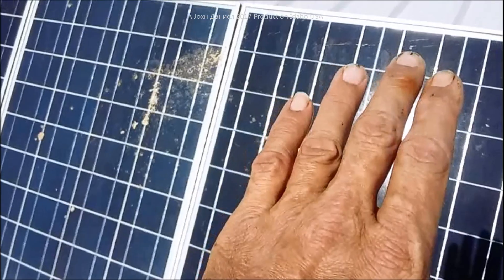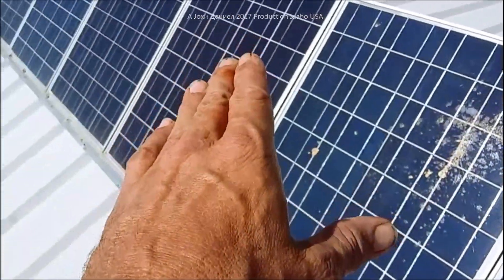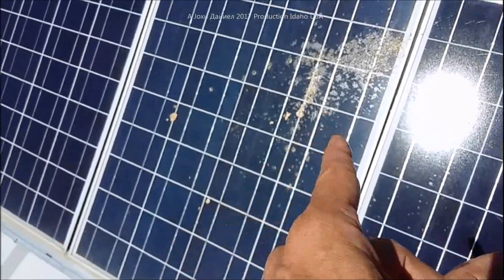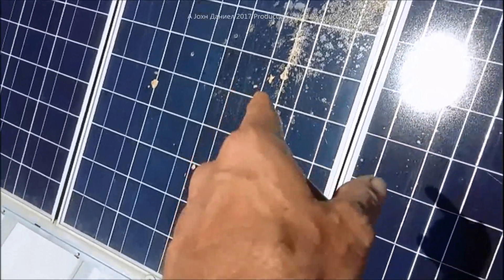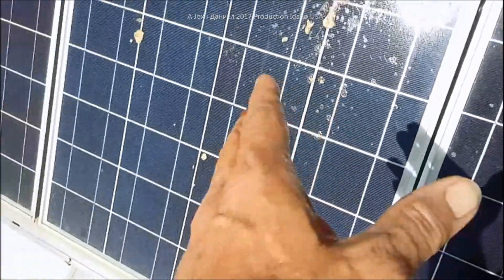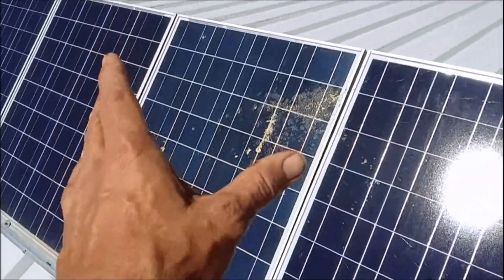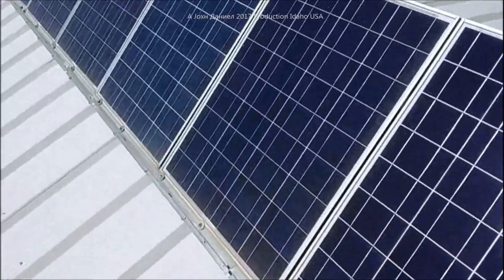This panel without a blocking diode would be taking the load of one, two, three. Since it would be less voltage, these panels are going to be pushing against these bus wires, adding to increased amperage against that panel.